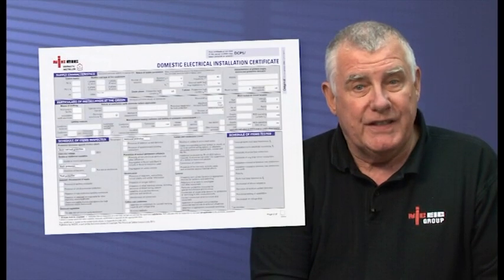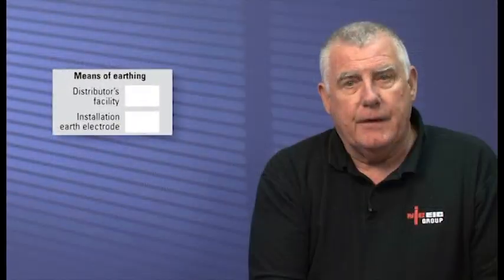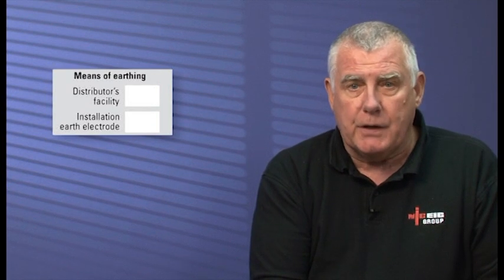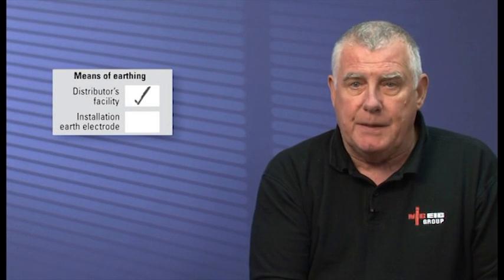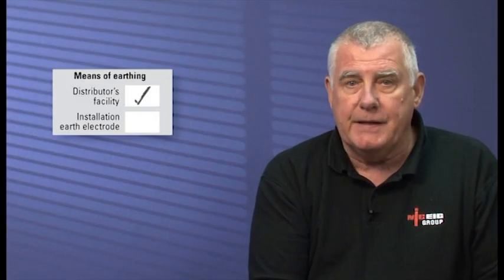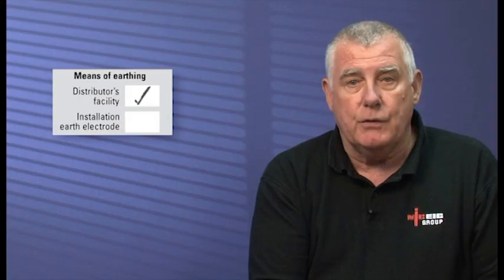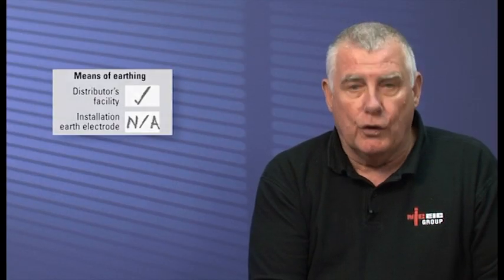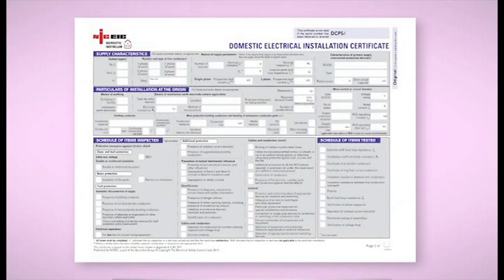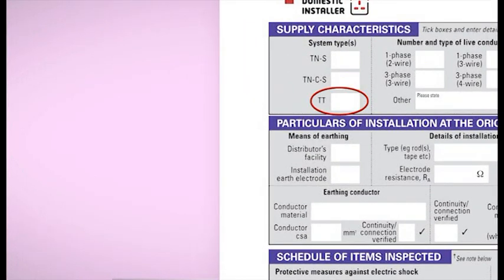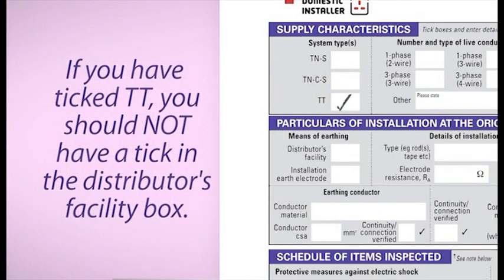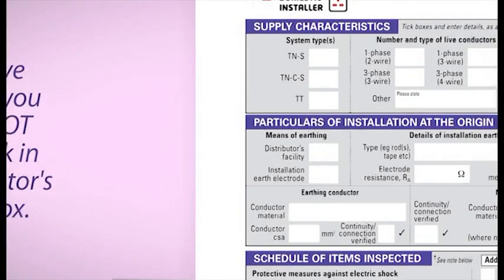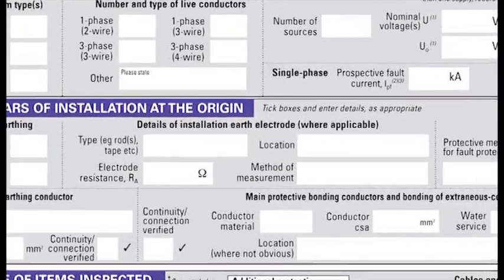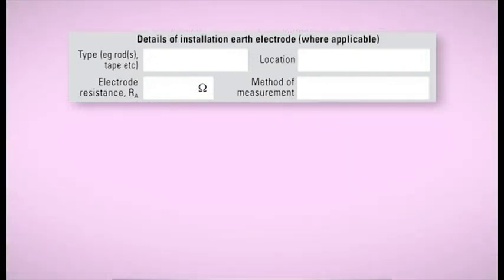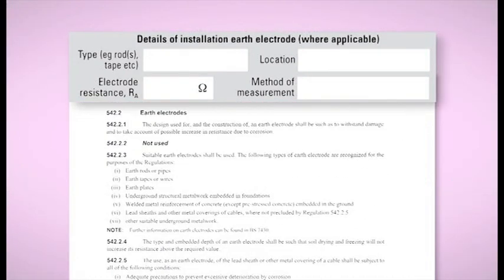The next group of boxes deals with the means of earthing. Now, if you have an earth provided by the electricity distributor and you tick the distributor's facility box, there is no need to fill in the remaining details about the installation earth electrode, other than to write none or not applicable. This should also reference the system type box. So, for example, if you've ticked TT, you should not have a tick in the distributor's facility box. However, you should insert a tick in the installation earth electrode box. If you're on a TT system, you'll have to fill in the remaining details about the installation earth electrode.